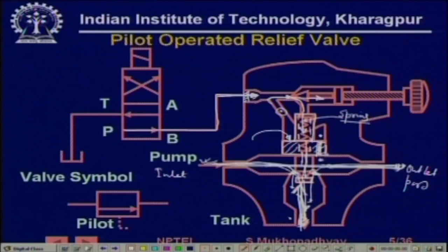So by applying a certain amount of pressure, you can decide the level of pressure at which this will drain to tank. So the relief level can be programmed. Such things can be done using pilot operated relief valves.